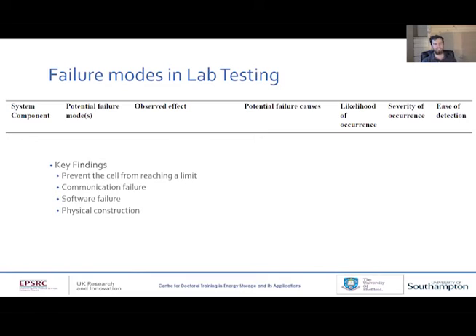So back to the failure modes. The key findings from that: as we already know, in general the aim is to prevent a cell reaching a limit, either voltage too high or too low, temperature too high, or current too high. Generally these battery systems are controlled by software, and failure of the system as a whole, i.e. one of these limits being reached, is most likely due to the failure of the software. That might be poorly written code or failure of the communication between different systems, such as the BMS, the power supply, and the PC that's controlling them. In addition, there's quite a high likelihood of failure when physically constructing the system, or maybe transporting it. For example, a short circuit from metal tools you might be using, or damage from dropping a pack.